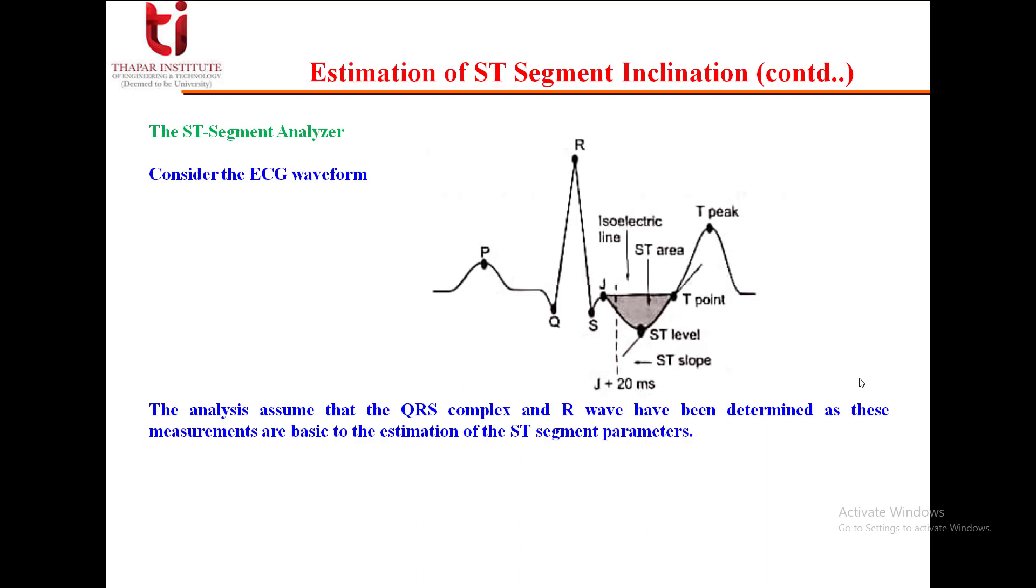Let's look at the ST segment analyzer. Consider this ECG waveform. You can see the ST area. We have taken one isoelectric line. The analysis assumes that the QRS complex and R wave have been already determined with the previous methods. These measurements are basic to the estimation of the ST segment parameters. For an accurate estimation of the ST segment, one needs to define the J point. The J point corresponds to the change in the slope.